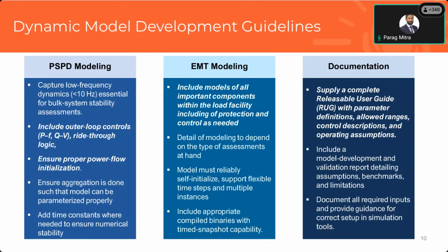The power flow conditions are the initial conditions for any kind of phasor domain positive sequence model. So we need to make sure that the power flow is initialized properly, and from the power flow, the model gets initialized. So when we're developing these models, we need to make sure that that exercise has been done properly.